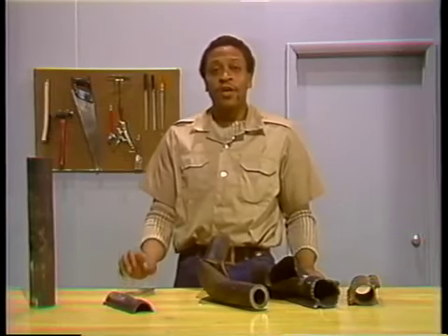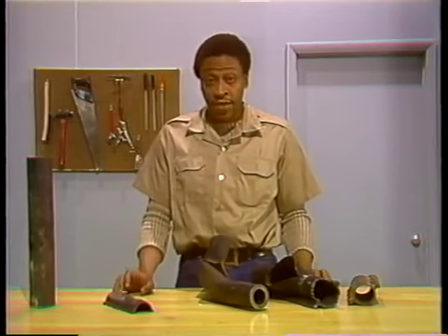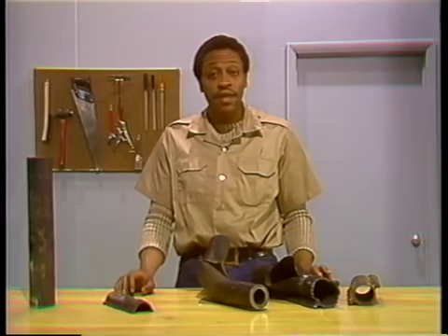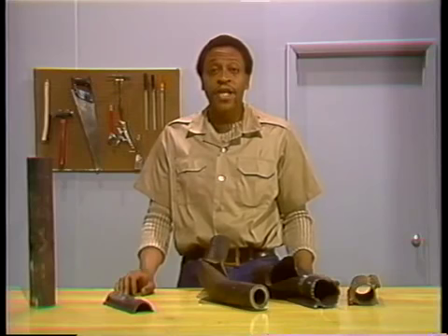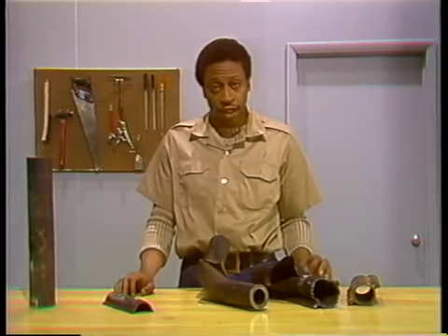Three more failures you may run across are fatigue cracks, tearing of tube metal at weld patches, and the tearing of tube metal at support clip attachments. Fatigue cracks are caused by mechanical stress. They appear as clean, bright breaks through the tube.